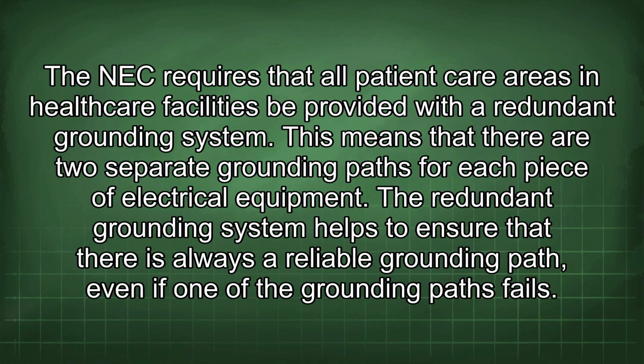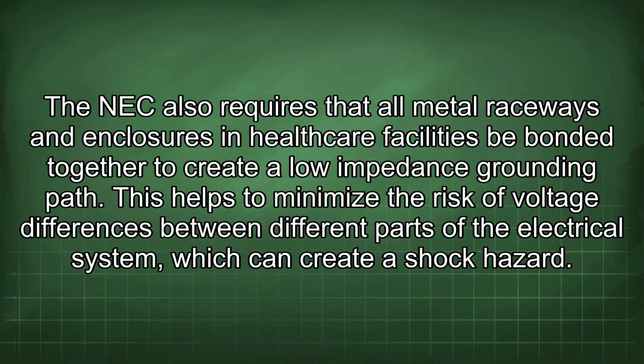The NEC requires that all patient care areas in healthcare facilities be provided with a redundant grounding system. This means that there are two separate grounding paths for each piece of electrical equipment. The redundant grounding system helps to ensure that there is always a reliable grounding path, even if one of the grounding paths fails. The NEC also requires that all metal raceways and enclosures in healthcare facilities be bonded together to create a low impedance grounding path. This helps to minimize the risk of voltage differences between different parts of the electrical system, which can create a shock hazard.